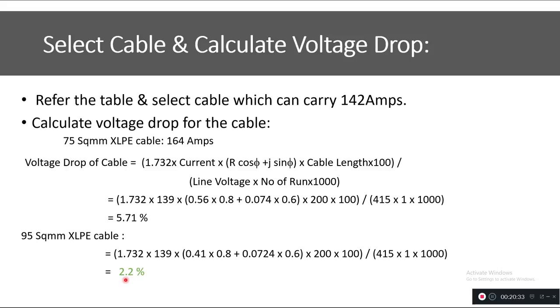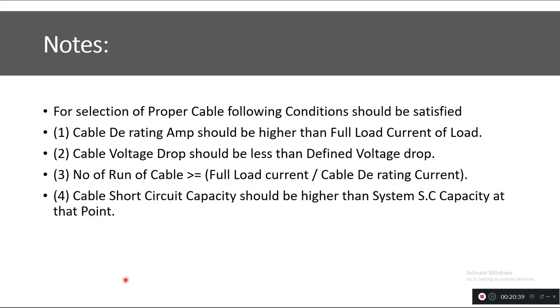Before finalizing the cable, you should verify four conditions. First, the cable's derated current capacity must be higher than the full load current — which we confirmed. Second, the cable voltage drop must be less than the defined limit of 5% — which is satisfied at 2.2%. Third, the number of cable runs: in this example we used one run, but if multiple runs are needed, calculate it as full load current divided by cable derated current.